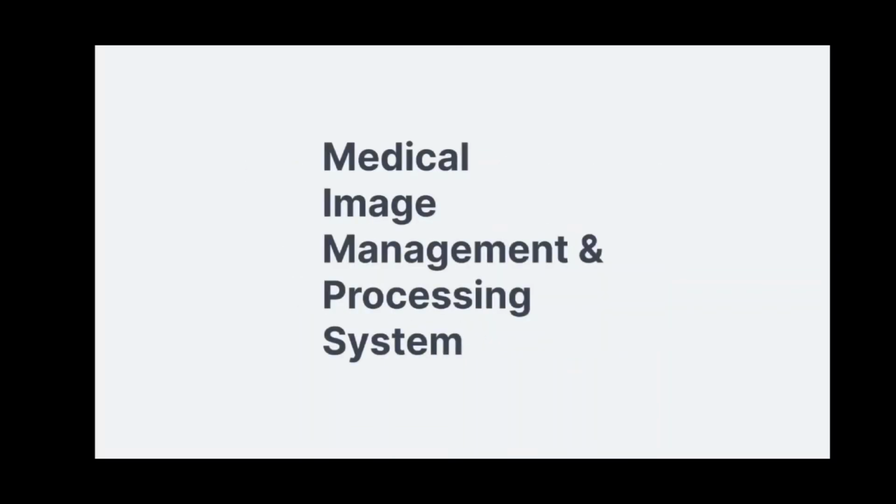However, if a software function allows for a practitioner to manage patient care through the processing, manipulation, enhancement, or review of patient images or information, it is regulated by the FDA. And that's why MIMS makes more sense. It stands for Medical Image Management and Processing System.